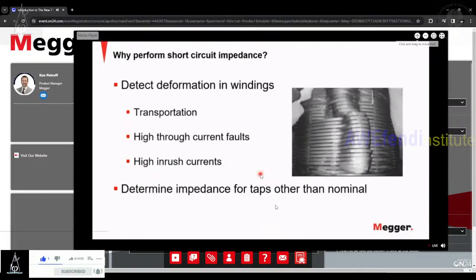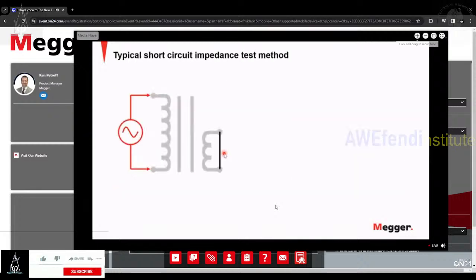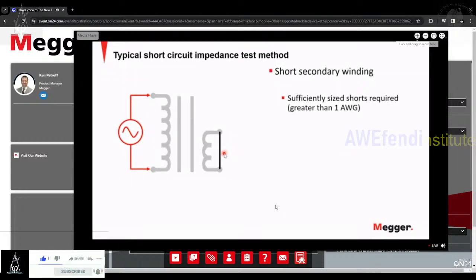And this is just an example of what some transformer windings may do when they experience certain conditions out in the field due to faulting, where this sort of buckles out like this. And that's what we're looking for. The typical short circuit impedance method, how Megger did this before in the MLR10 product, we would apply a short on the secondary winding.